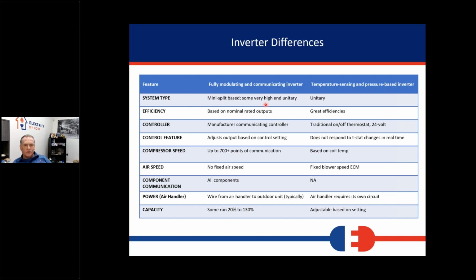The mini split based unit is a little bit more efficient, does give you some more flexibility. Both of these are going to really deliver great efficiencies. The mini split stuff, their efficiencies are based on what they call their nominal output.